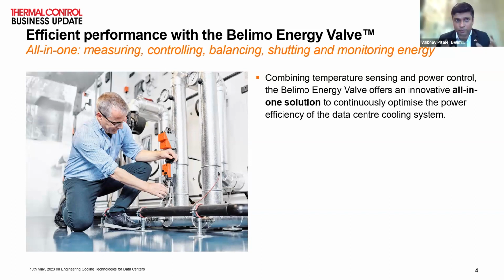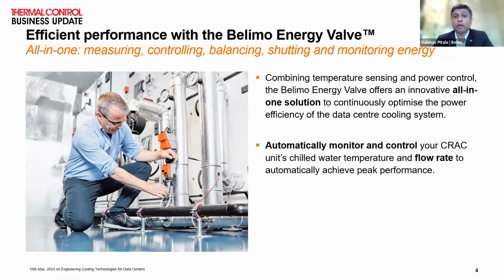So just imagine if you are able to have measuring, control, balancing, shutting down, as well as monitoring of energy in one solution, with automatic control and monitoring of CRAC units. Managing the flow is very important, because the principle of cooling, the thermal energy, depends on the flow rate. We don't design the valve based on the DN size, we design the valve based on the actual flow.